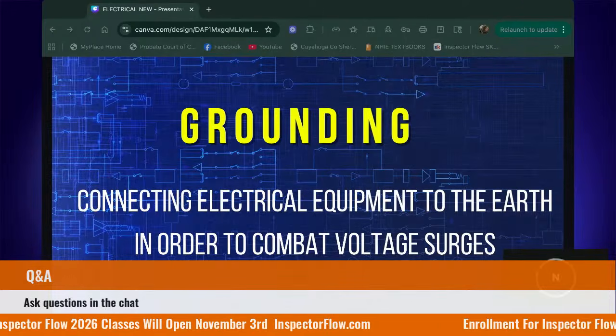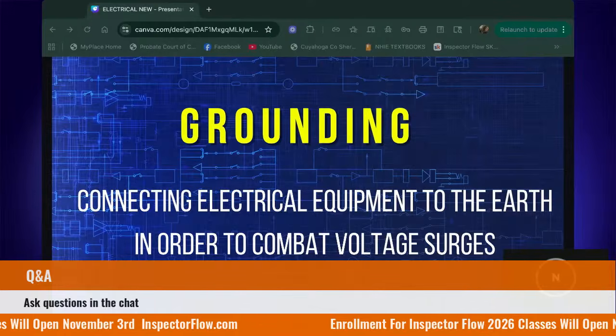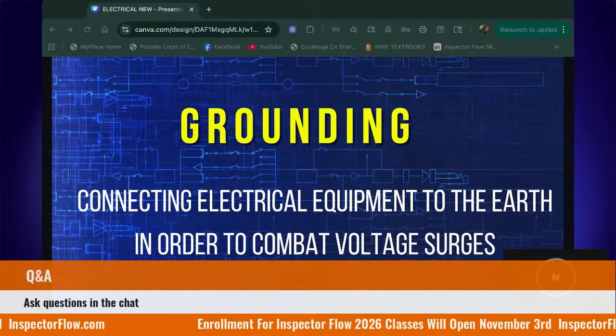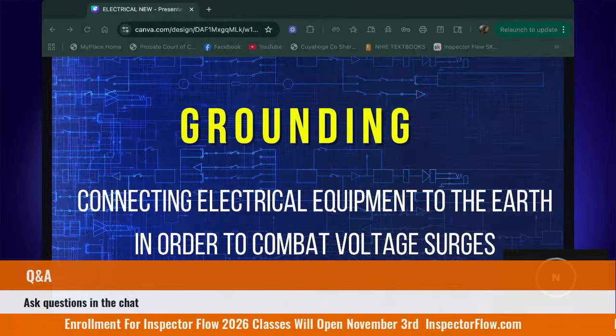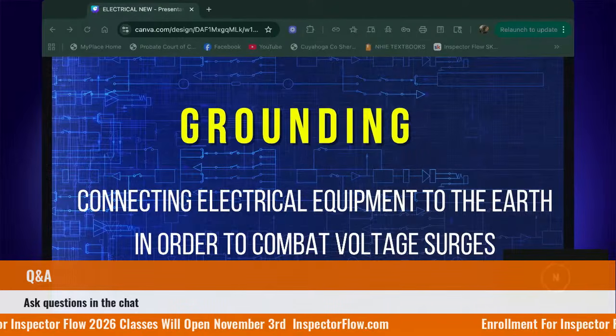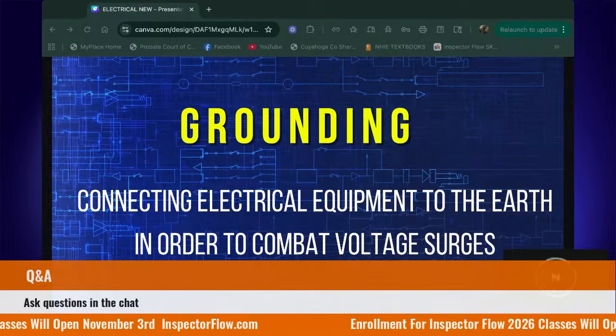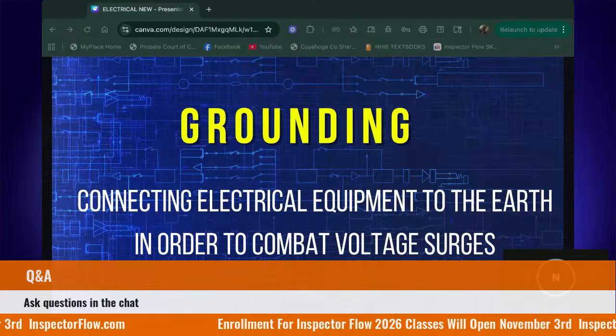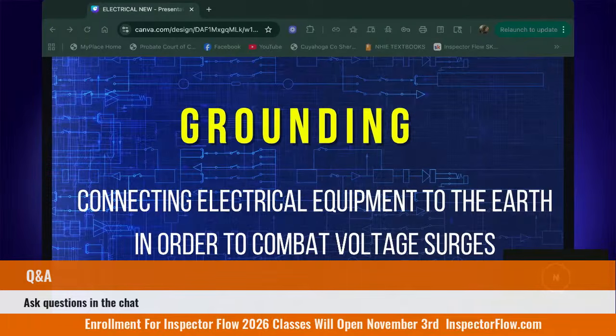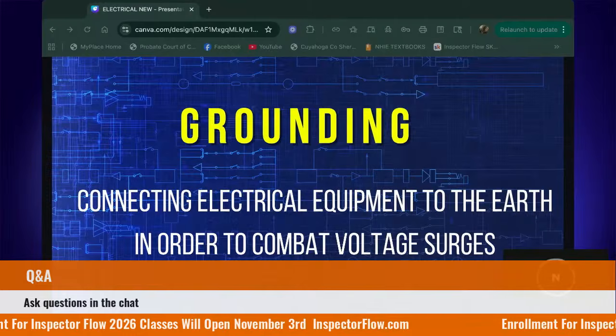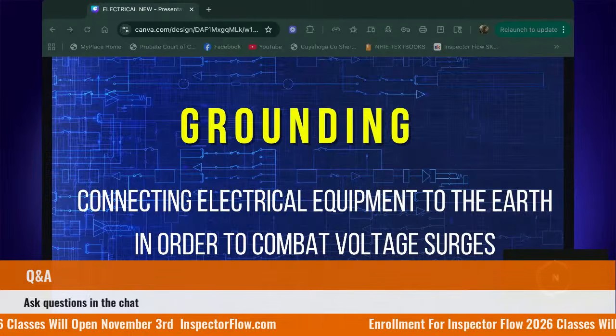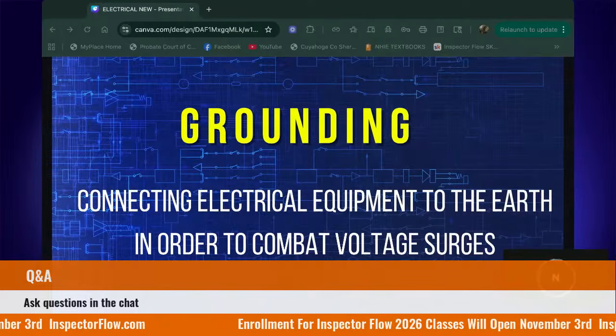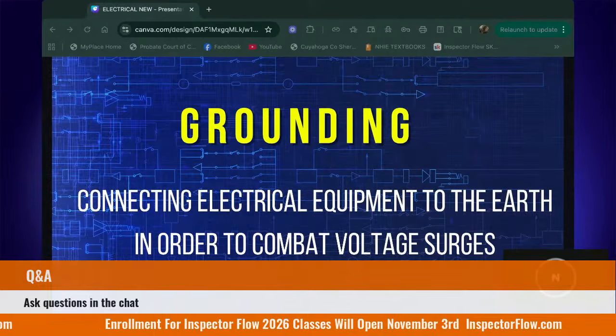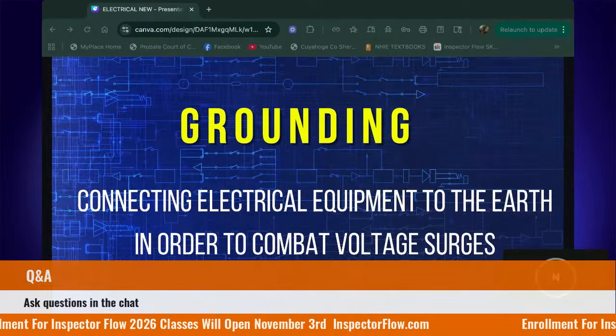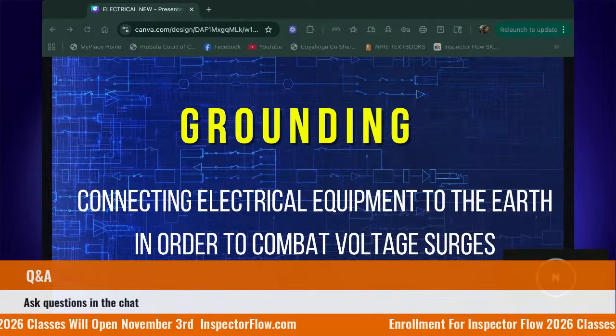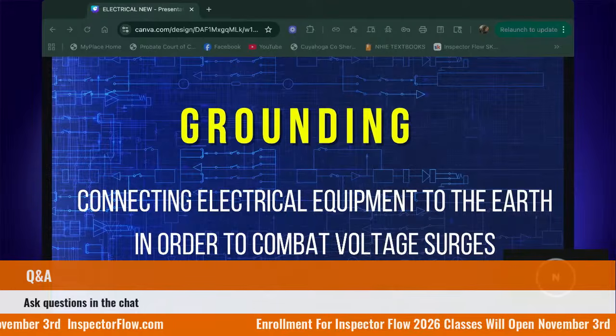So this is why our neutrals and our grounds are only connected together one time at the main service panel. Our neutral is supposed to be carrying our current back to the source. When we say source, we're speaking of the transformer. Our neutral is supposed to be the way that we're carrying it back. But if there's an issue, then our grounding system would need to step in and provide a path.